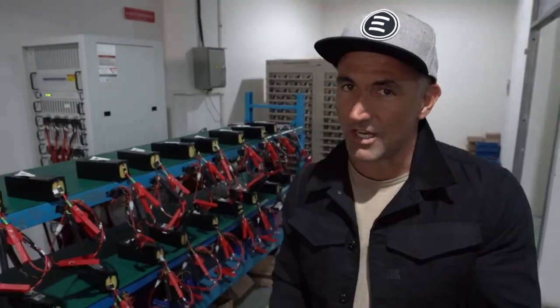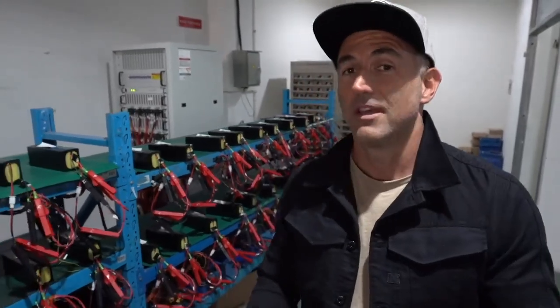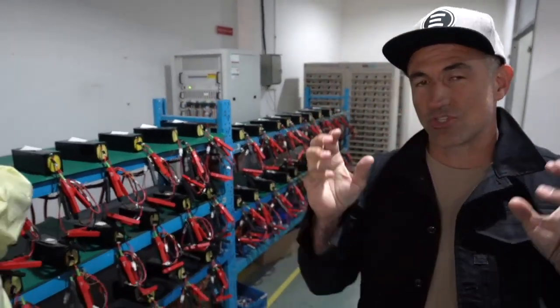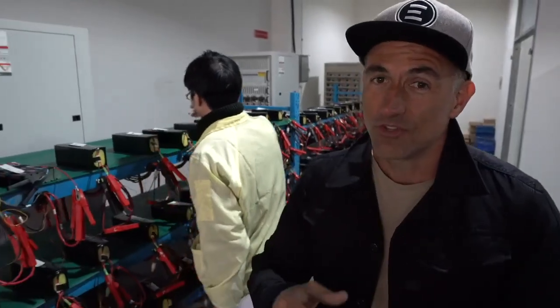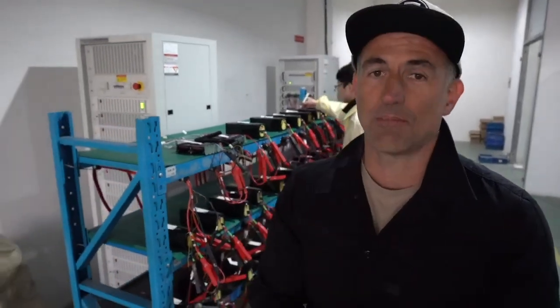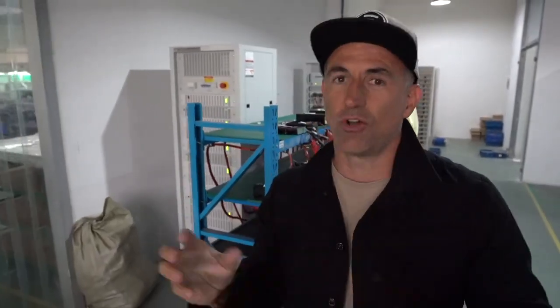Once the vibration test is complete, the next step is we discharge and then recharge the battery two times over. Once that's done, we let the battery sit for 7 days. During that time, each day we check to make sure the cells are still balanced and no voltages have gone out of whack. Once we've got the tick, the last step is we turn the battery on and give it one last charge. As long as it's all good, we then send it over to packing for us to assemble into our skateboards.